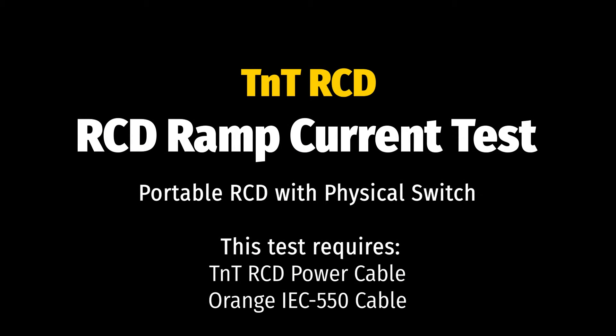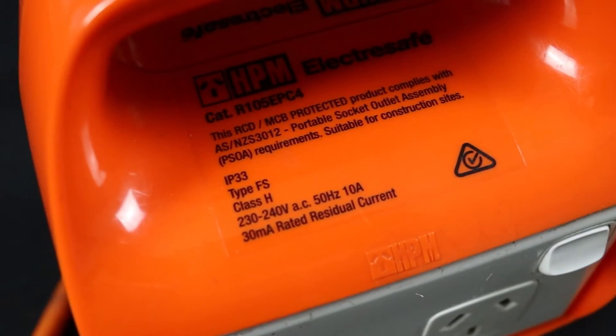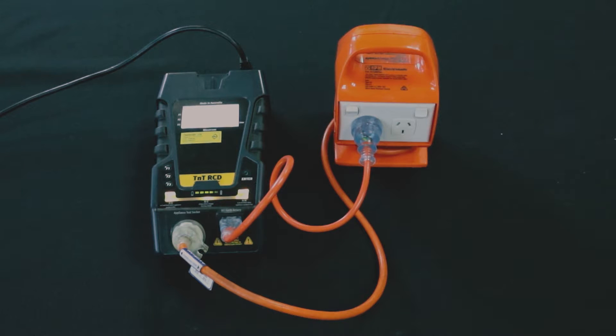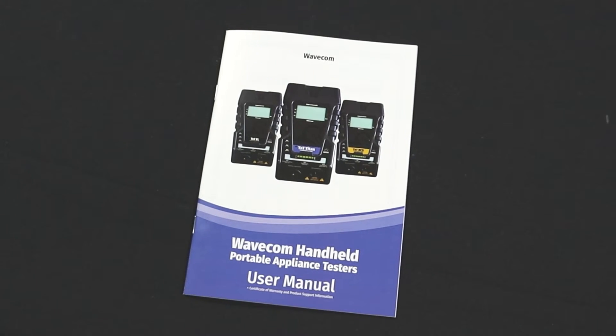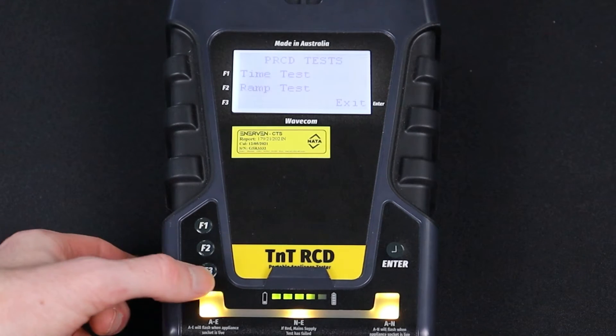Let's move on to testing portable RCDs. We'll start with a ramp current test. First, conduct your visual inspection and determine what type of RCD you have. This example is a Type FS portable RCD. Set up your test leads — in this example, we are using the updated test method. If in doubt, consult your TNT-RCD user manual. Navigate to the main menu using the Enter button, then press F3 to enter the RCD menu.